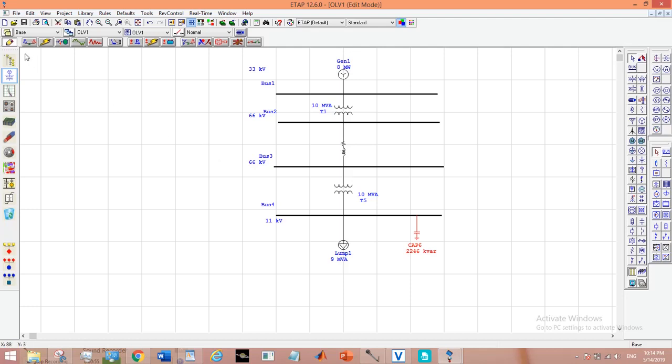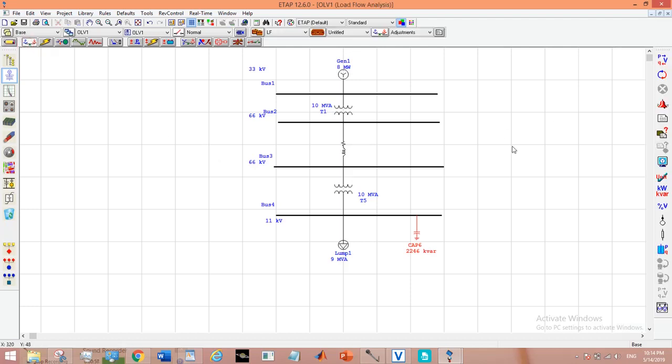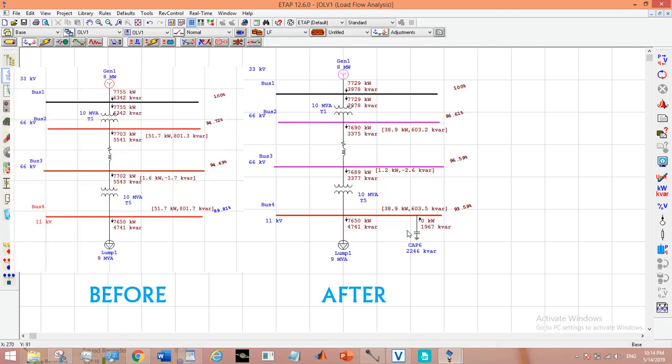Now let's again go to the load flow analysis and run the load flow. What we observe is that the capacitor is providing the kVARs and the kVARs coming from the generator, they have reduced.